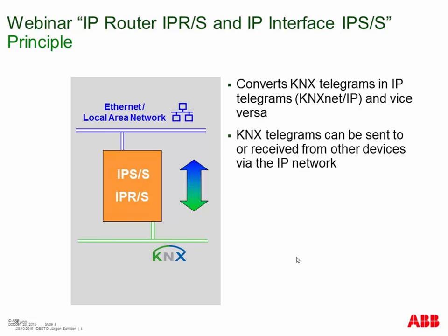What is the task of an IP interface? We have the IP router and the IP interface. First of all, it's a connection between the twisted pair KNX bus cable and the local area network, the Ethernet in your building. The task is to convert KNX telegrams into IP telegrams and vice versa, so communication is possible in both directions. We have the standard protocol on the twisted pair bus cable, but also the KNXnet/IP protocol on the Ethernet part.